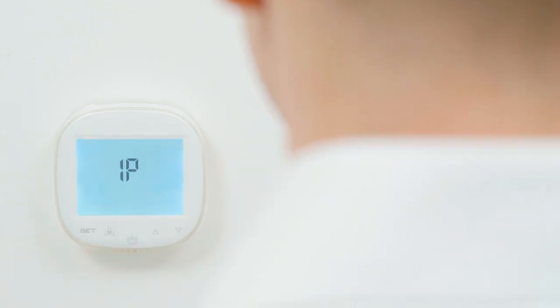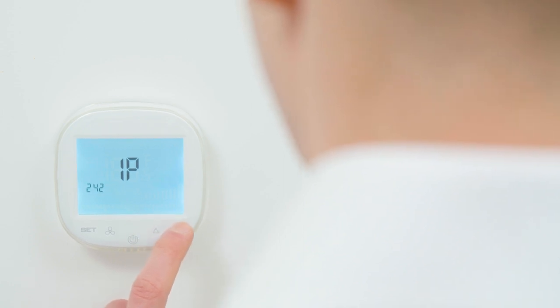In this part of the video, you will learn how to configure the advanced settings of the HMI Volcano EC controller dedicated to Volcano units with EC motors. Holding the fan button and the down button longer will allow us to go to the first part of advanced settings. It is important to remember that when you hold down these buttons, the controller has to be off. The markings correspond to the functions specified in the controller manual. Change the values of the individual functions by pressing the up and down buttons and press the set button to switch to the next function.